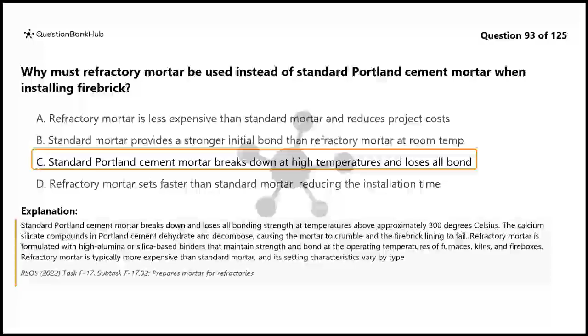Standard Portland cement mortar breaks down and loses all bonding strength at temperatures above approximately 300 degrees Celsius. The calcium silicate compounds in Portland cement dehydrate and decompose, causing the mortar to crumble and the firebrick lining to fail. Refractory mortar is formulated with high alumina or silica-based binders that maintain strength and bond at the operating temperatures of furnaces, kilns, and fireboxes. Refractory mortar is typically more expensive than standard mortar, and its setting characteristics vary by type.